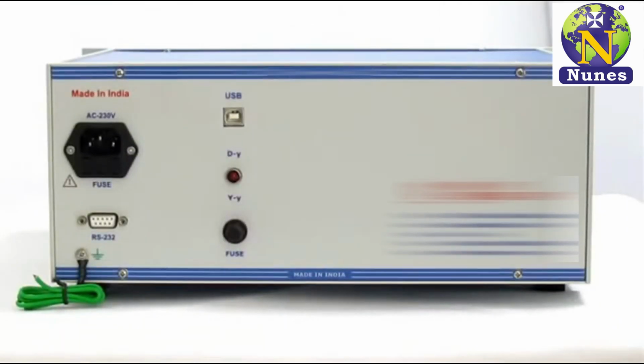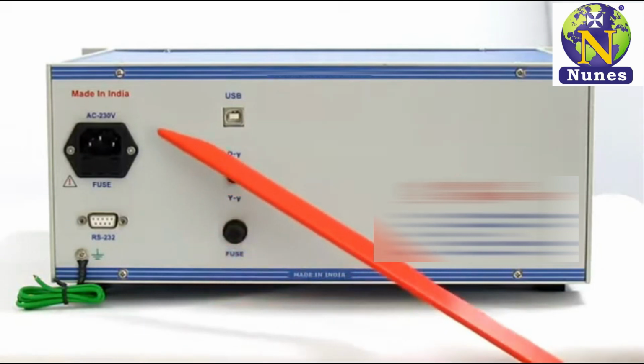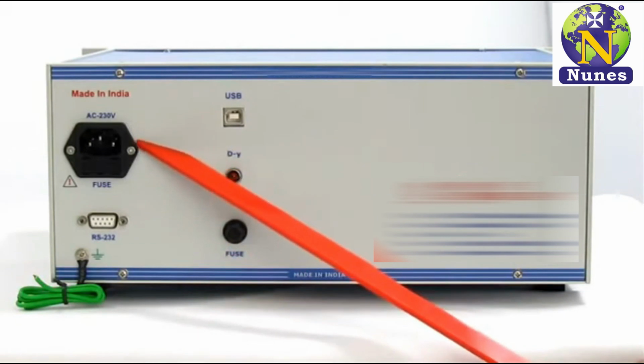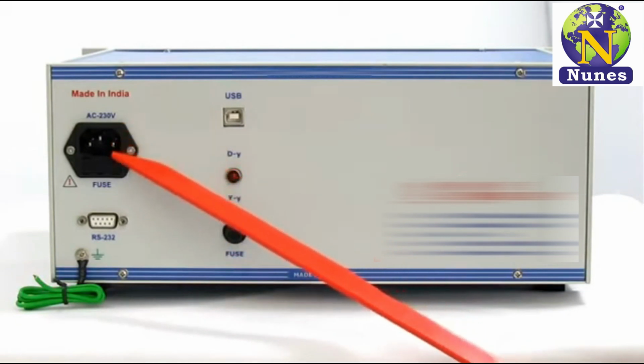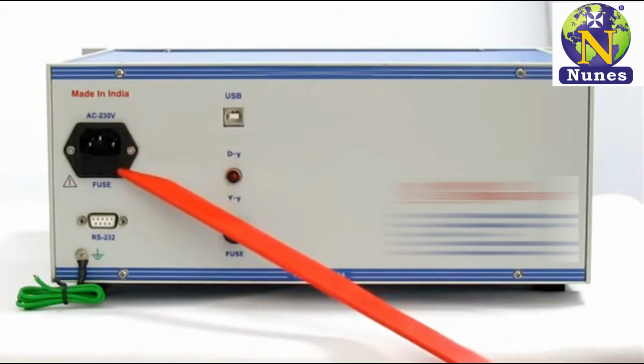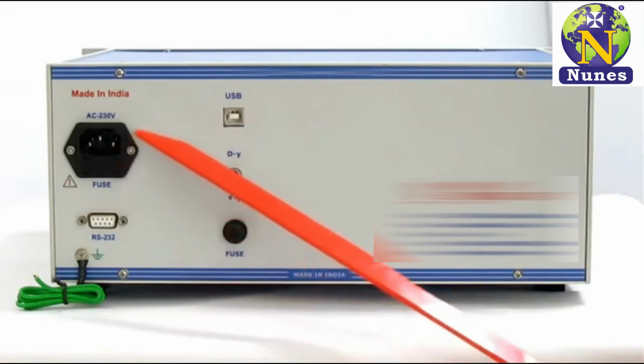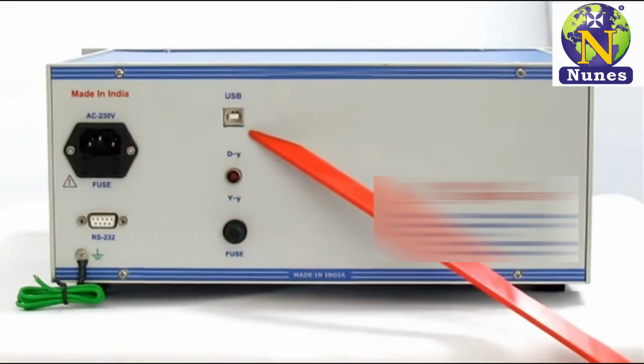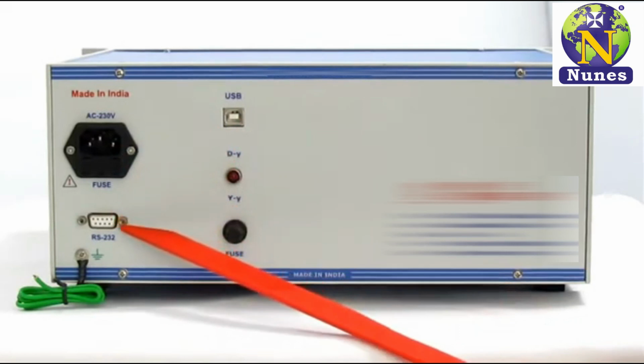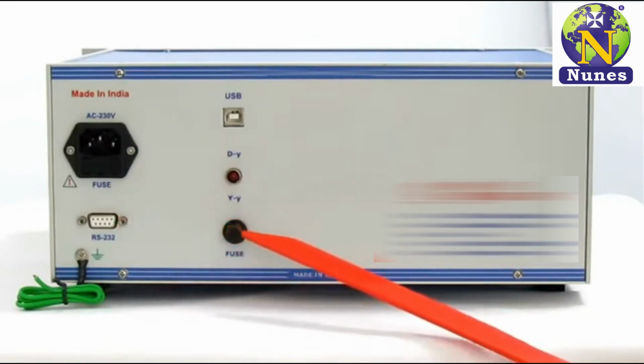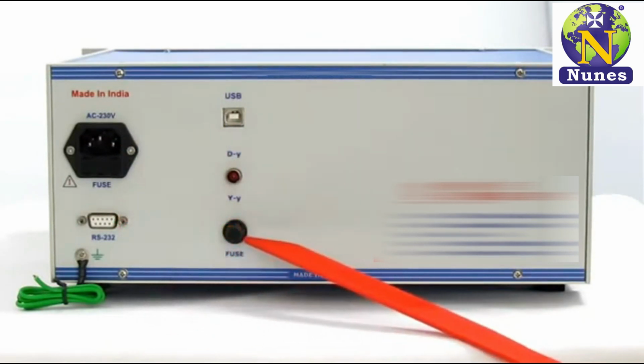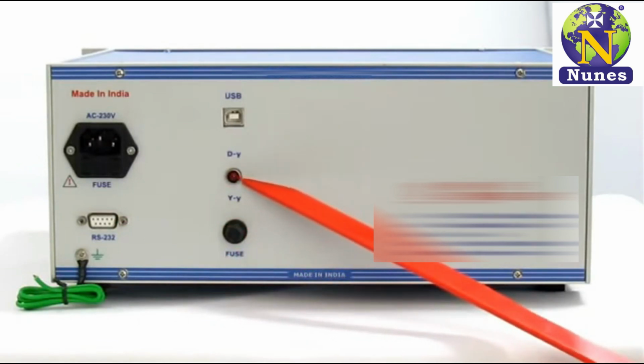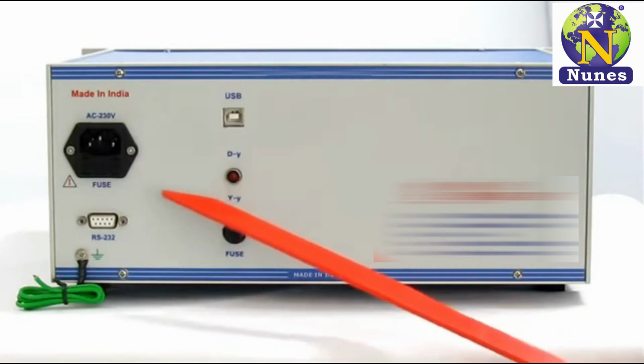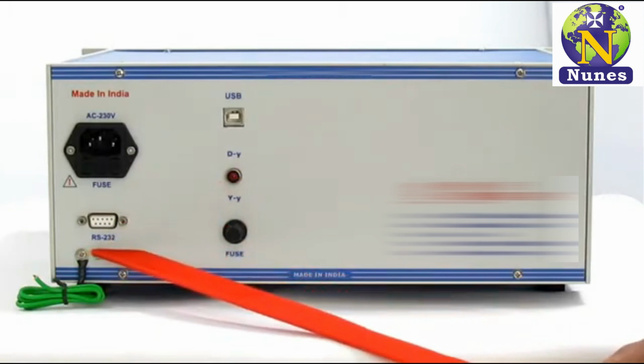Here you can see the rear panel of the transformer turns ratio meter. In the rear panel, first one is the auxiliary power supply 230 volt AC socket with 250 mA fuse protection. Next one is USB and RS-232 ports. Then the testing fuse of 1 amp and LED indication for fuse blown. This is the earthing terminal.